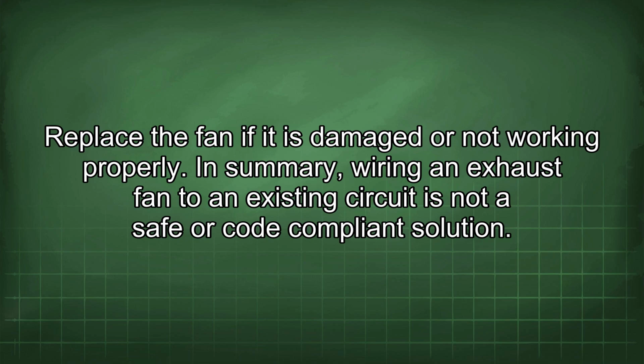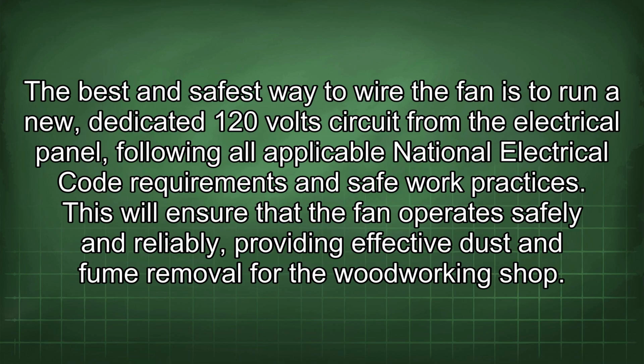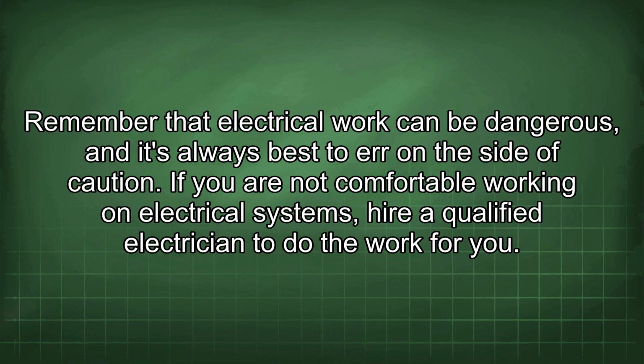In summary, wiring an exhaust fan to an existing circuit is not a safe or code-compliant solution. The best and safest way to wire the fan is to run a new, dedicated 120-volt circuit from the electrical panel following all applicable National Electrical Code requirements and safe work practices. This will ensure that the fan operates safely and reliably, providing effective dust and fume removal for the woodworking shop. Remember that electrical work can be dangerous, and it's always best to err on the side of caution. If you are not comfortable working on electrical systems, hire a qualified electrician to do the work for you.